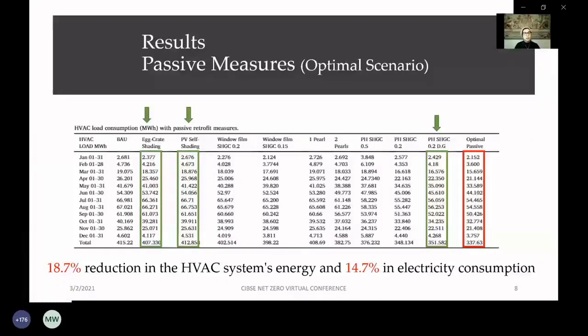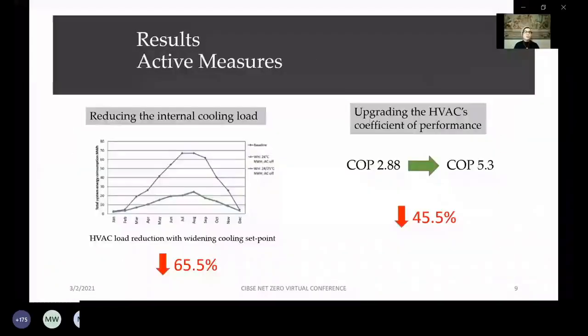Active measures, reducing the internal cooling load and upgrading the HVAC coefficient of performance, both provide a very impressive result. Combining passive and active measures to form an optimal retrofit, the result was also really encouraging: the cooling system energy was reduced by 83%, and the electricity reduction was 65%.